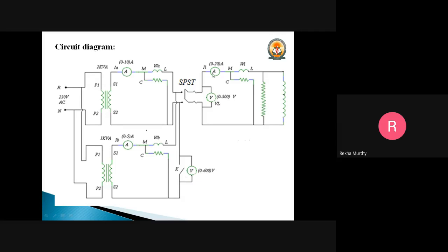So decrease the load to 0, then open that SPST switch to remove the load and then open the supply. So perform similarly the short circuit test on both the transformers to determine their equivalent impedance. The short circuit test is conducted on each of these two transformers separately, with the meters connected onto the primary and the readings tabulated. So for these two transformers, we need to conduct the short circuit test separately.